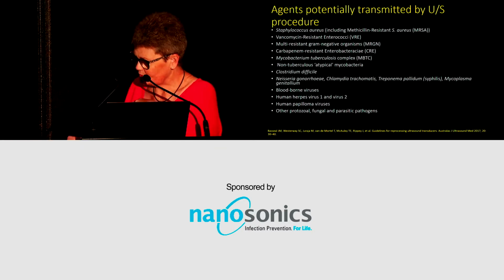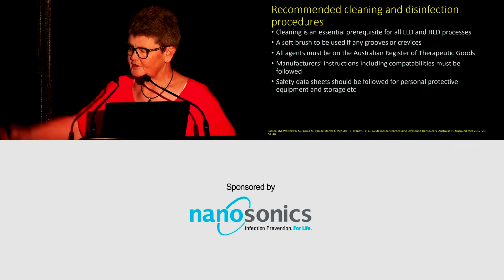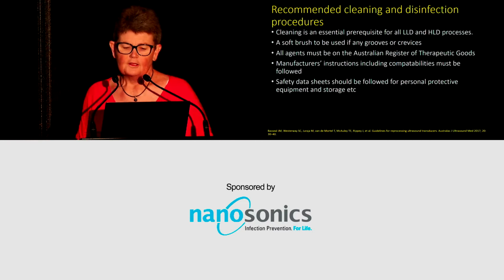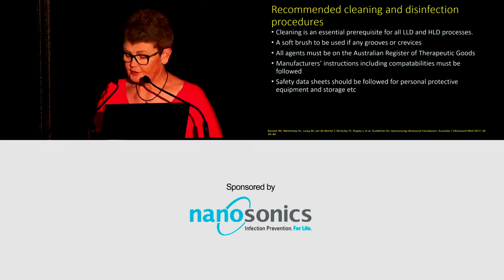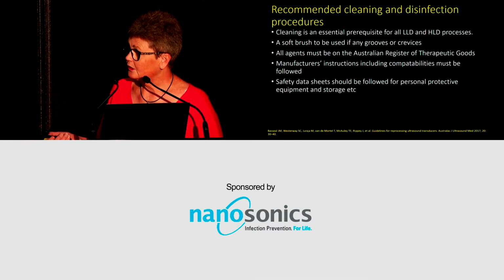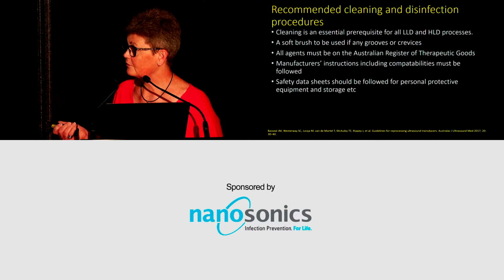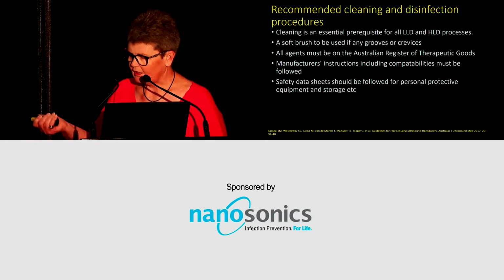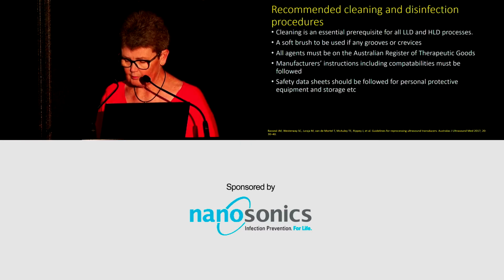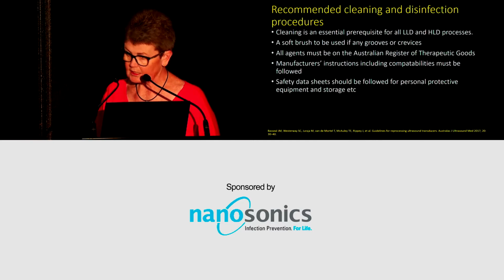So I've kept building the case this morning, and thank you for persisting with me, but it's serious when you see such a broad range of organisms. So what are the recommended cleaning and disinfection procedures according to the ASIPSI ASUM document? Cleaning's essentially a prerequisite. A soft brush should be used, particularly in grooves and crevices, to get rid of any bioburden in there. All the agents that we use must be on the TGA Register of Therapeutic Goods. Manufacturer's instructions, including compatibilities, must be followed, and safety data sheets should be followed so that staff have personal protection, and as well they need to have equipment stored appropriately, and I would imagine auditing of that is also important.